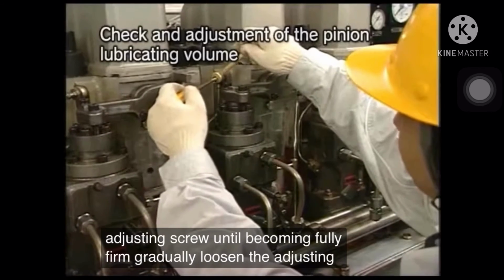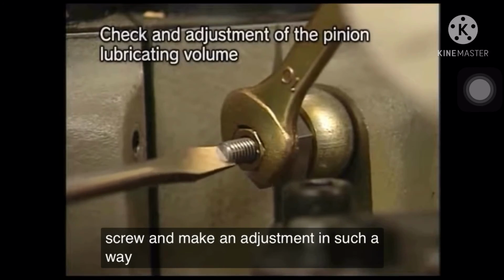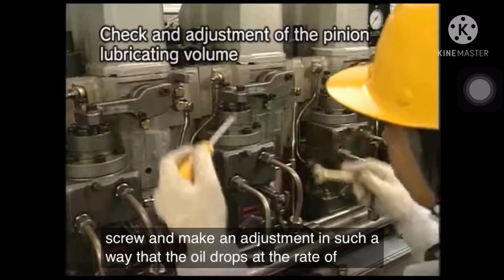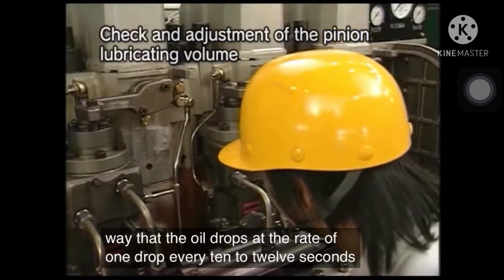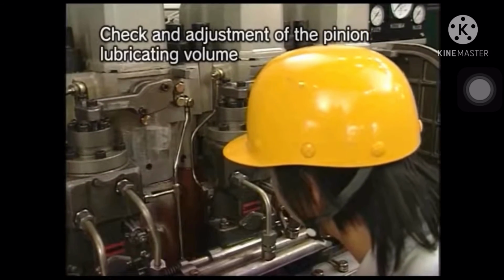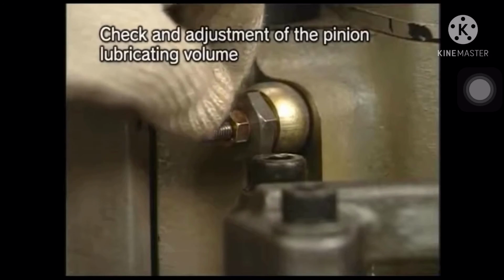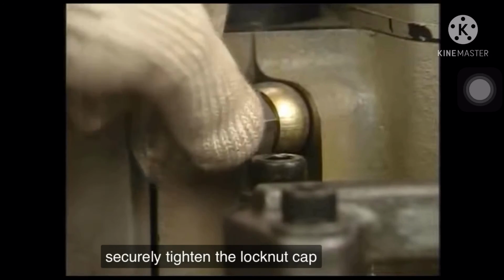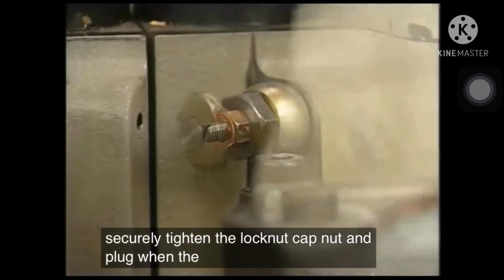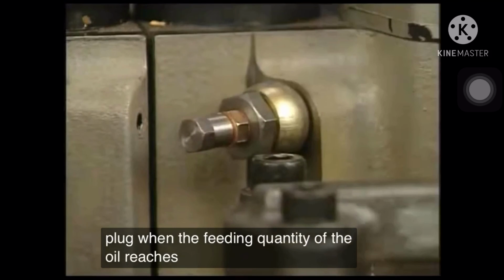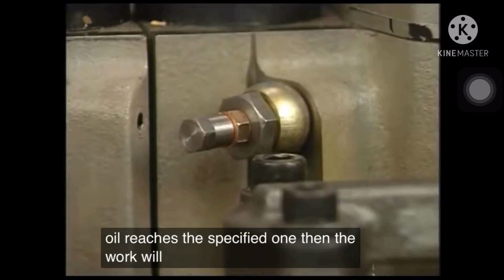Gradually loosen the adjusting screw and make an adjustment in such a way that the oil drops at the rate of 1 drop every 10 to 12 seconds. Securely tighten the lock nut, cap nut, and plug when the feeding quantity of the oil reaches the specified one, then the work will be completed.